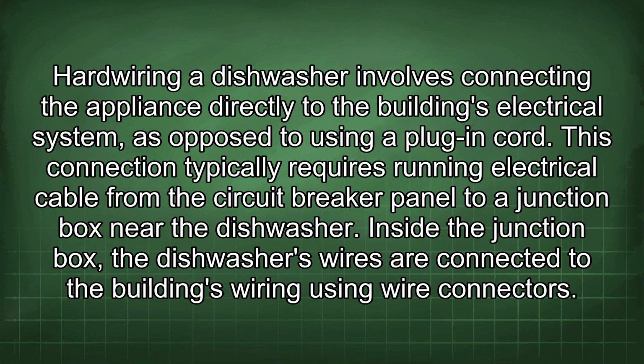Hardwiring a dishwasher involves connecting the appliance directly to the building's electrical system, as opposed to using a plug-in cord. This connection typically requires running electrical cable from the circuit breaker panel to a junction box near the dishwasher. Inside the junction box, the dishwasher's wires are connected to the building's wiring using wire connectors.